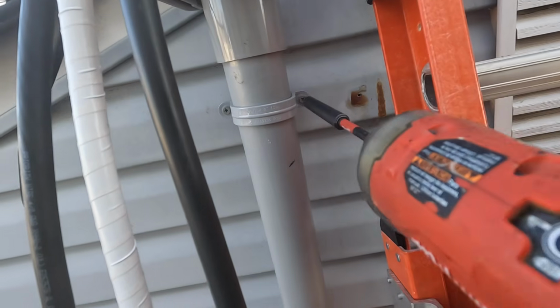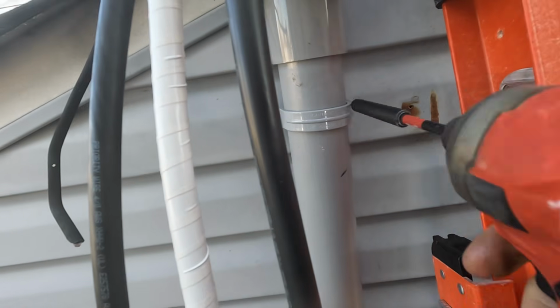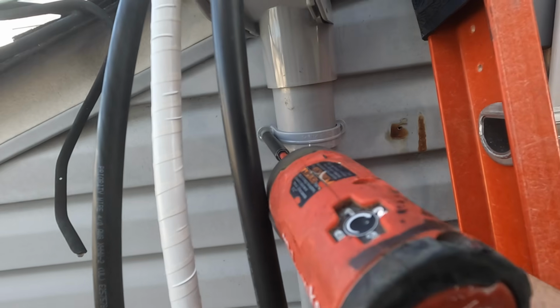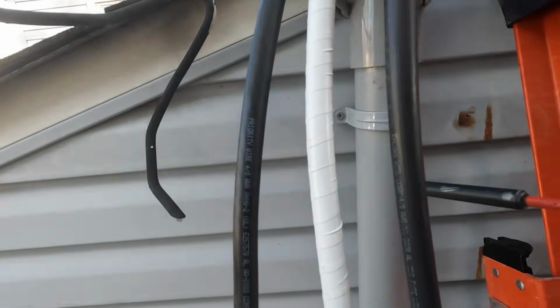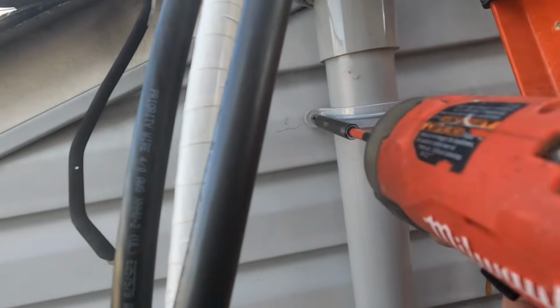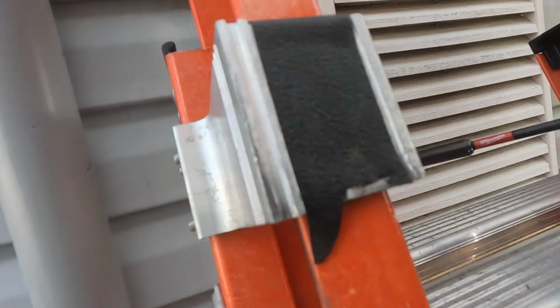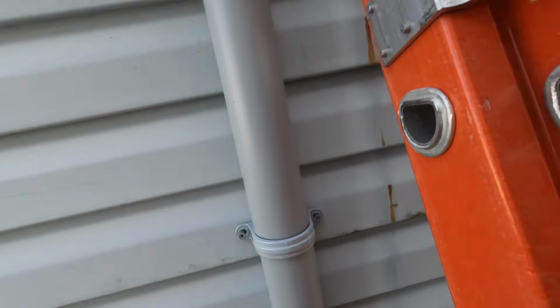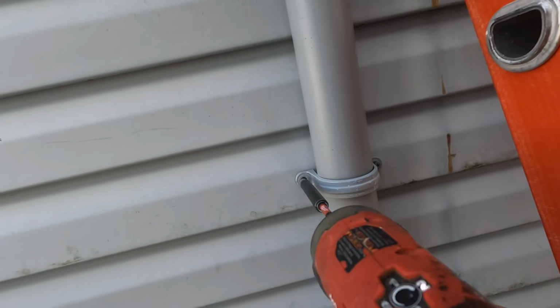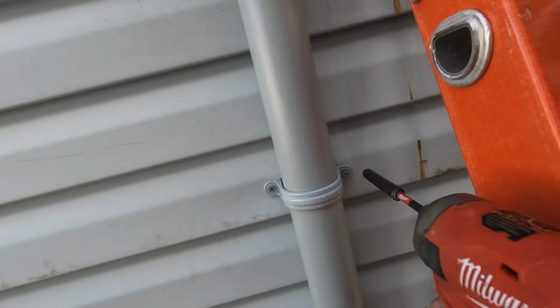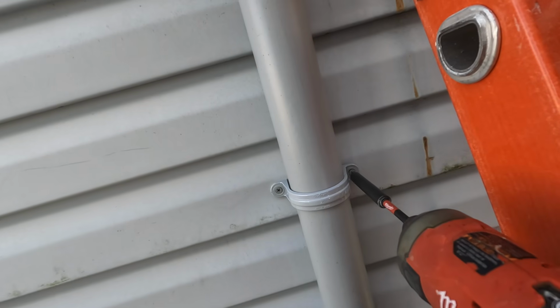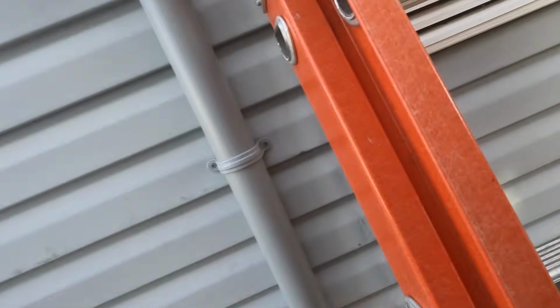Now I can secure the conduit riser back properly to the house, which is what I'm doing here. And then shortly we'll be tying in our service entrance conductors to the service drop. Now, when you're making the connection to the service drop, you just want to make sure that you do not complete the path to ground. So you don't touch a hot conductor to something that's grounded, which is why electricians use fiberglass ladders, because they're non-conductive.